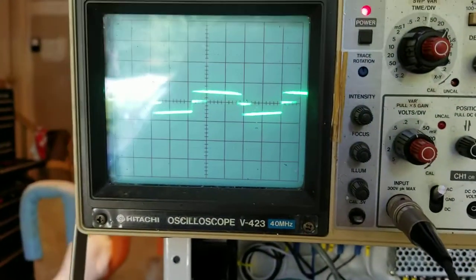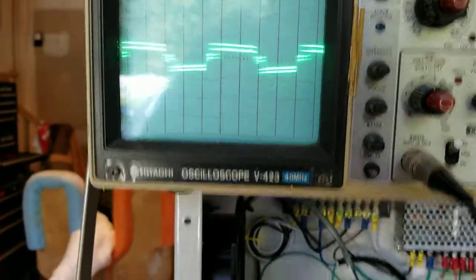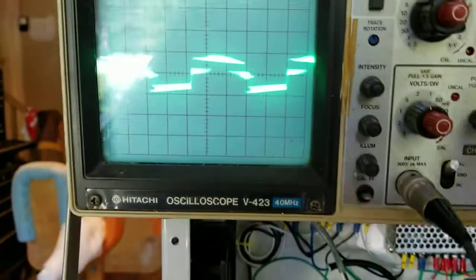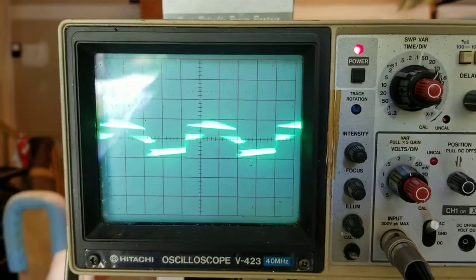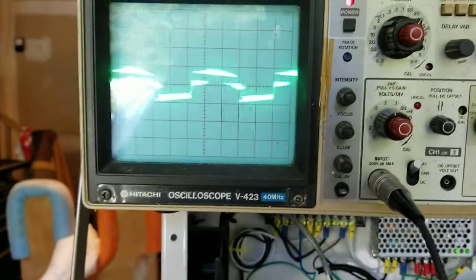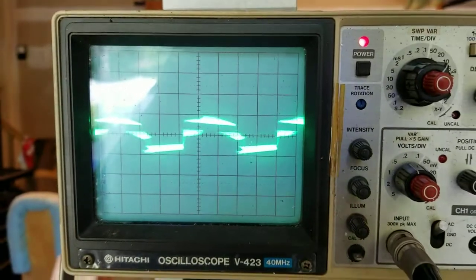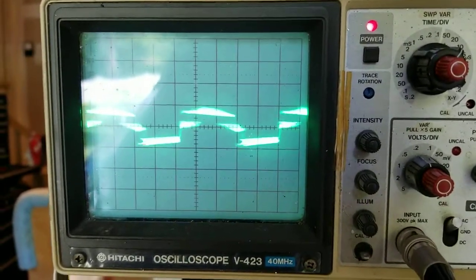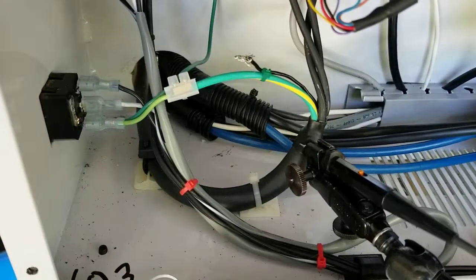Now we're at 0.2 volts per division. Let's go back to 1x there. 0.2 volts per division. That's coming in—I measured previously—about 0.32 volts peak-to-peak. So that is right outside the VFD jacket.